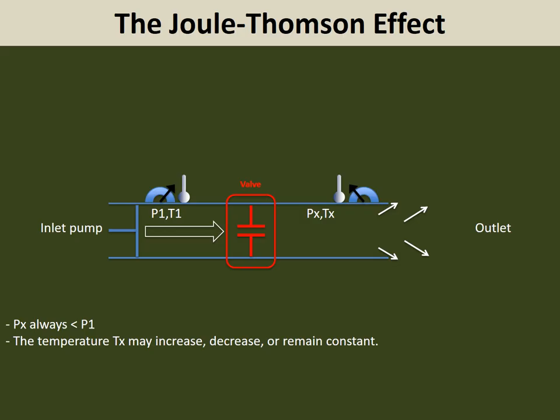To start, let's review the principle of the Joule-Thomson effect. You may wonder how the equipment you are using can deliver cold and freeze the tissue. In real world, the Joule-Thomson effect is a thermodynamic process that occurs when a fluid expands from high pressure to low pressure across a valve. Under the right conditions, this can cause cooling of the fluid.